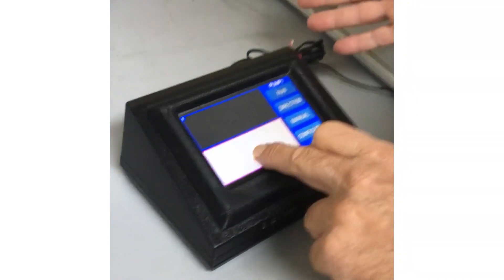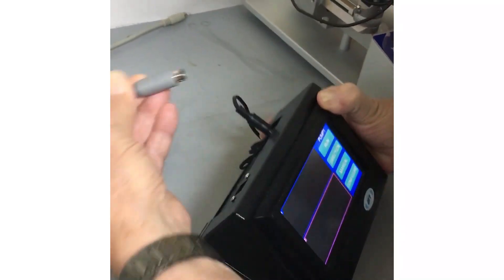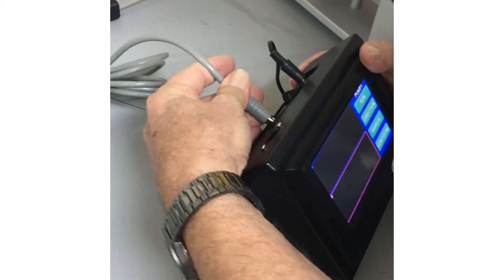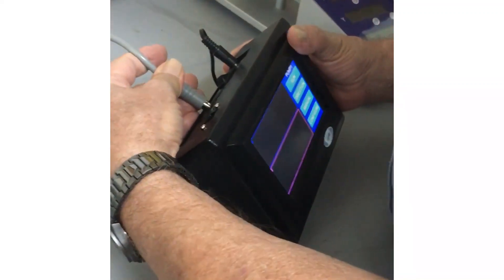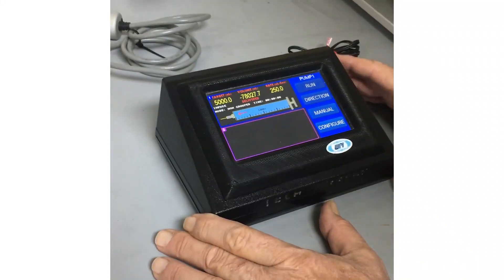You get this page here, and then you go to display all channels. That's normally. Now there's nothing here. I can select either pump one or pump two. What I want to do is take a pump and plug it into channel one. You have to look for the arrow — the arrow is always up on this gray cable — and stick it in there. Now as soon as you do that, this screen comes up, so you can select that screen.